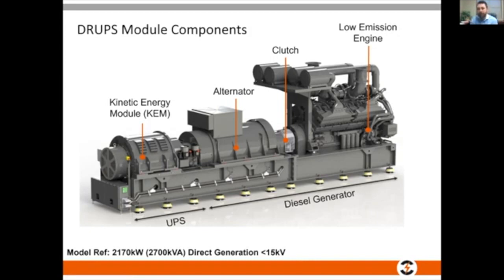Also worth noting that a standard, by example, 2.2 megawatt diesel generator, if you were to buy it in a container, is about 40 foot long by about 9 to 12 foot wide. Well, my Drups, also at 2.2 megawatt, will also fit in a 40 foot container, 9 to 12 foot wide. So if you are looking for outdoor applications, I offer significant footprint savings because now I've saved all the room inside the building that would otherwise be allocated to the batteries, to the rectifier, to the inverter, to the air conditioning, to the control panels. So we have this a power block that we call it, which is our container.